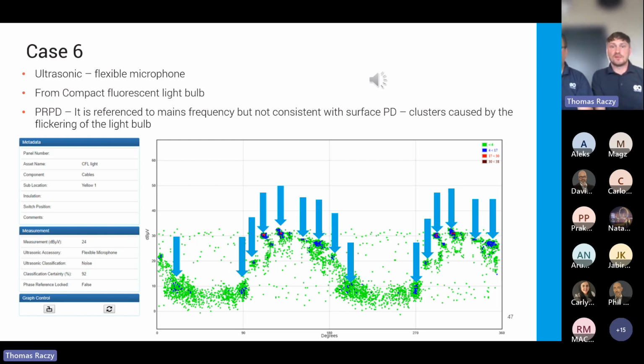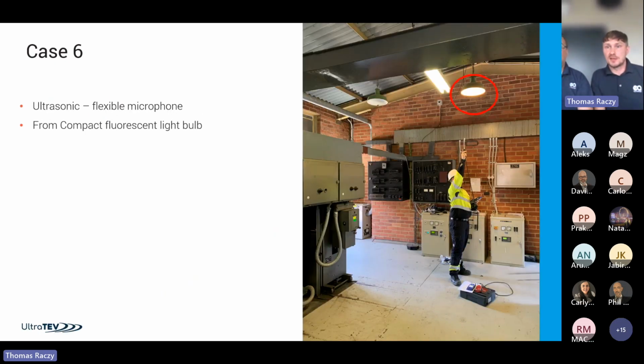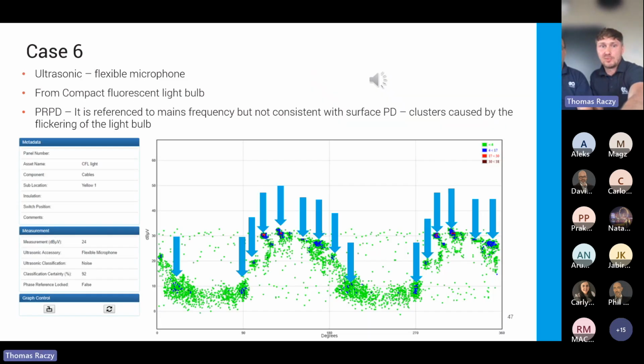built up from loads of individual clustering of the signals. The reason why it builds up the patterns is because it's a light bulb that operates at 50 or 60 hertz. So it will follow the mains frequency. It's powered by mains, but the sound of it is completely different. It's almost like a high pitch transformer buzzing, and the repetition rate will be definitely different to the actual PD, as well as the fact that it's primarily built up on loads of different clusters of events.